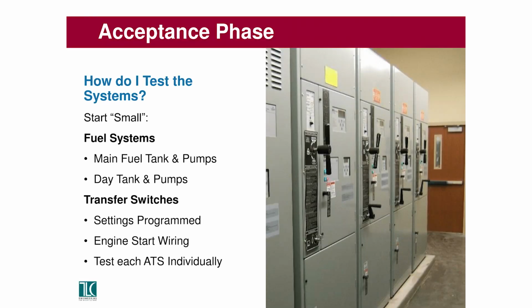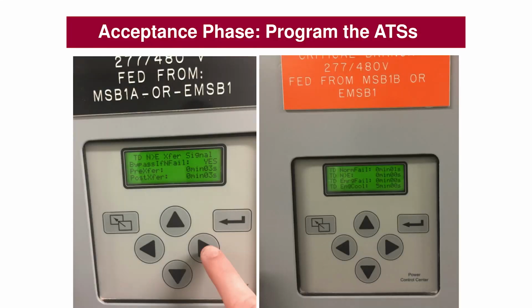Another way to put it is that we start small. We test each of the components. All those different system components that I've been talking about, we test them one at a time. We test the fuel systems, we test the main tank and the day tank pumps, and then we test the transfer switches, all the wiring, and then test each transfer switch individually. Usually we're making sure that they've all been programmed first.